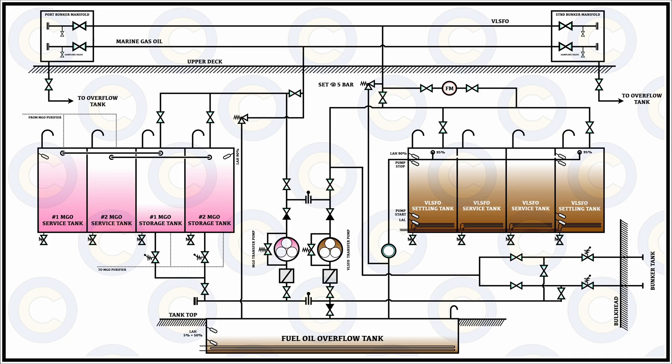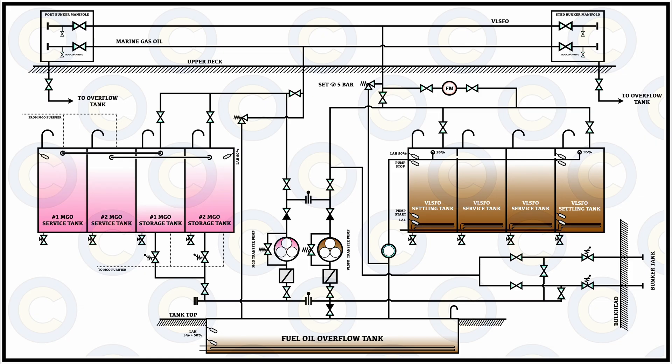On the heavy oil side, that is basically now what we regard as the LSFO, we will again be drawing suction from the dedicated bunker tank by opening this main suction valve from the bunker line. The oil would come and wait over here basically at the end of the transfer pump. Then lining up the suction and discharge for the transfer pump and main discharge valve, you will now be having your oil available to be filled in the dedicated settling tank. Accordingly you can open whichever settling tank valve that you want to fill the oil inside and then start the transfer pump to make sure that the oil flows from the right bunker tank into the right settling tank.